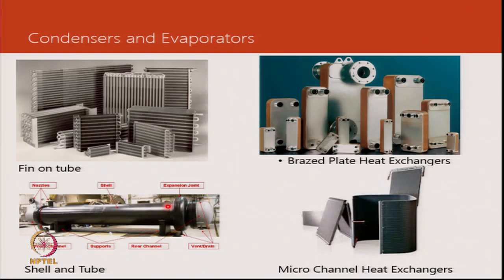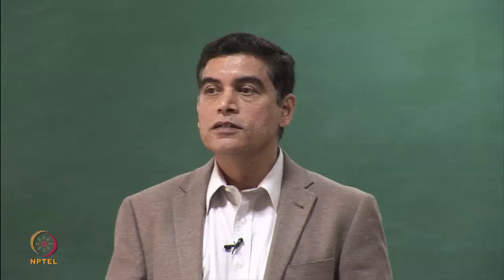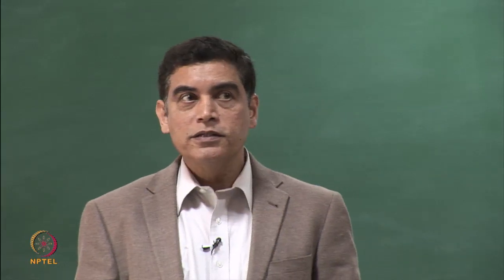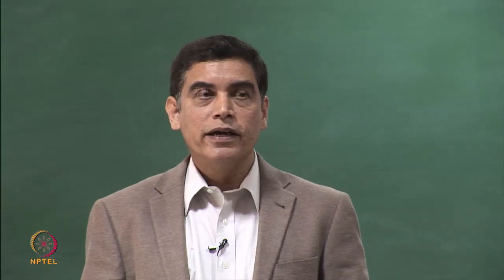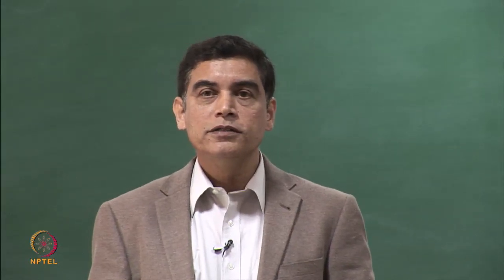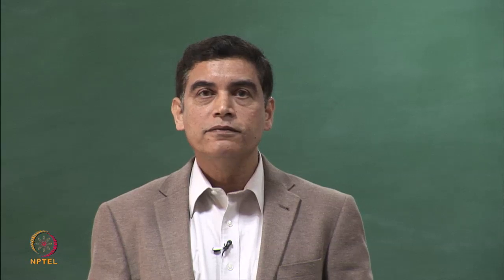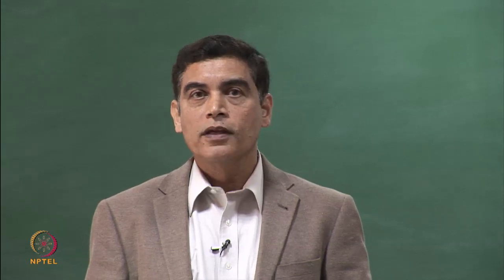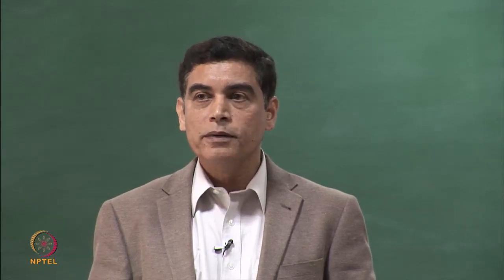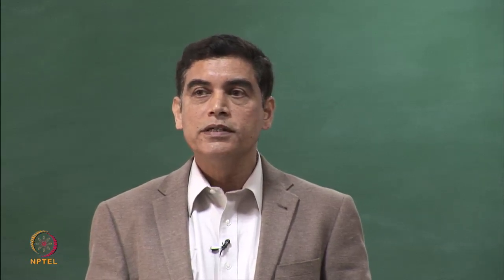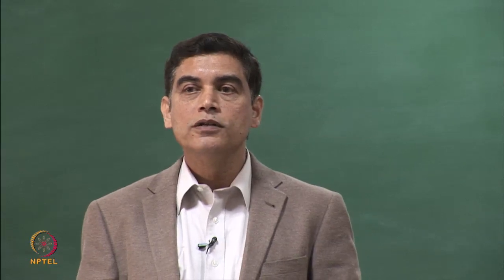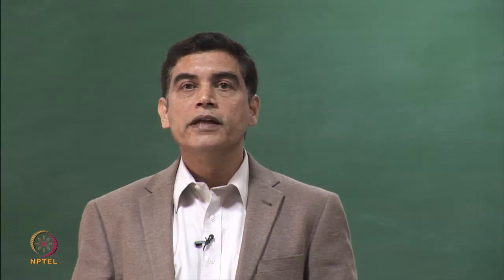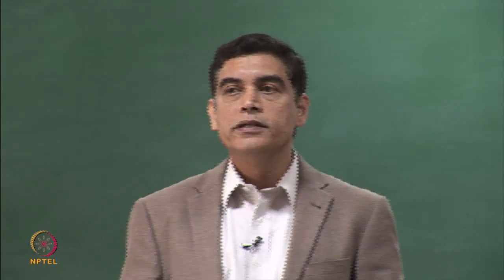Shell and tube condensers are the most conventional type and have been in use for a long time. They are easy to manufacture and fairly robust. They can handle very high pressures and temperatures, but they are expensive to build. So wherever the application permits, they have gradually been replaced by lower-cost alternatives like brazed plate heat exchangers.